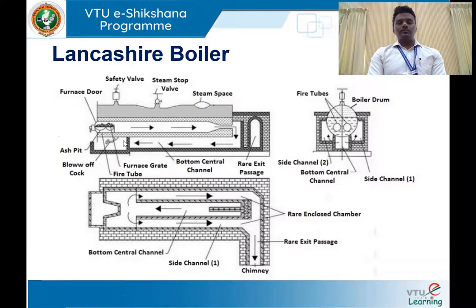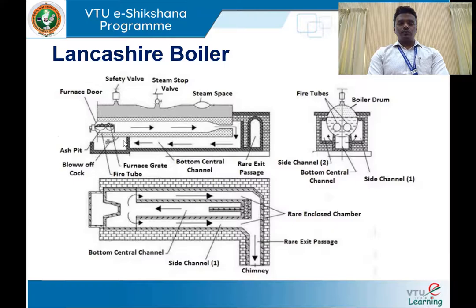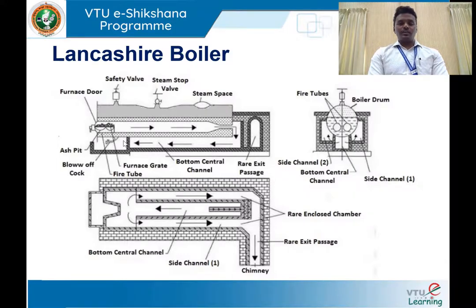Since water is used for steam generation, there will be many sediments, dust particles, and foreign particles. We need regular cleaning of the boiler shell. Sediments and solid contaminants collected at the bottom of the boiler shell must be removed periodically. Any operator can enter inside the boiler shell through a manhole on the Lancashire boiler. Regular and periodic cleaning can be done, and using a blow-off valve, we can replace the water and supply fresh water into the boiler shell, as well as remove sediments. To summarize, the Lancashire boiler is internally fired, low pressure, fire tube, and horizontal type.